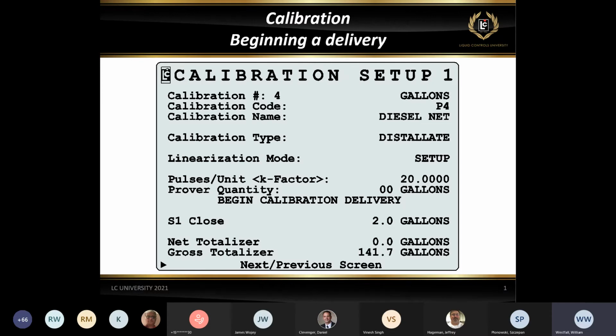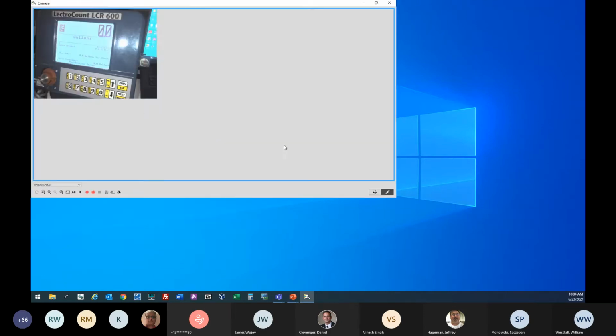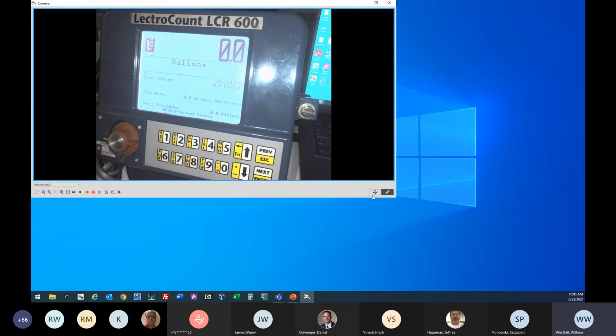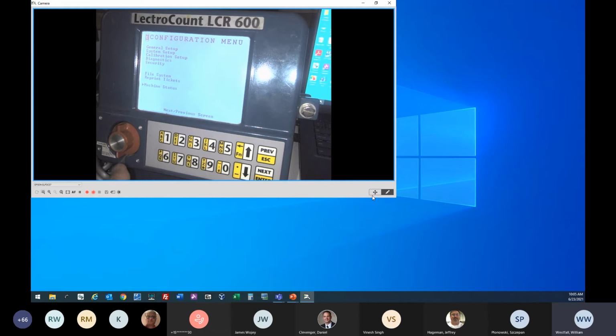Let me get to my camera here. Okay, hopefully everybody can see that. I had to do a little bit of a diagonal so I can get the light out of the way. There's a switch plate that goes around here. You're going to have to take those 4 screws off, and then turn that red knob straight up and down. You'll see that the red knob on the 600 and the LCR2 has a little white arrow, a little white line on it. That's the one that we want in the 6 o'clock position.